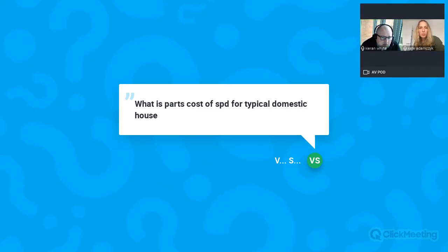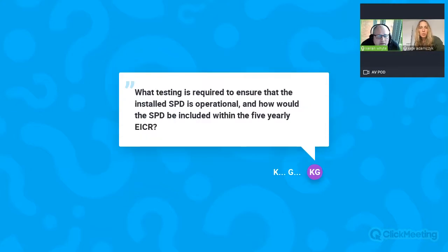So what testing is required to ensure that the installed SPD is operational? Well, on the front of our SPDs, we have a healthy signalling window. It'll be green under normal conditions, and it will go red once the device is end of life. As I said in the presentation, we're probably unaware of the amount of lightning strikes or even switching surges that our homes are currently exposed to. So it's almost like how long is a piece of string. You just need to tell the consumer to monitor it constantly. Say constantly, what's that, once a week? Maybe they go in the cupboard once a week or once a day to pick a coat out. So just keep an eye on it, and obviously notify the electrician then for replacement as and when it does go end of life.